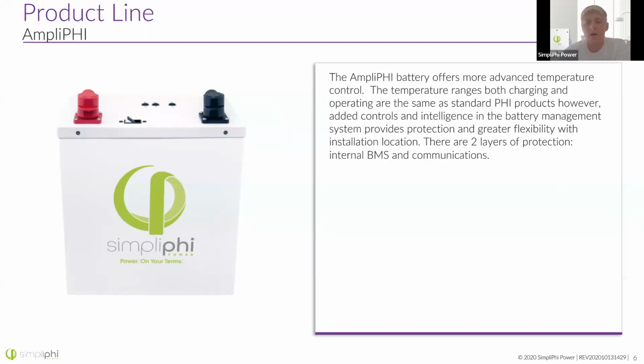The BMS provides two layers of protection. One layer is the actual communications ports on top. The battery will communicate with a compatible inverter charger, and in turn the inverter charger will listen to the battery's commands. So the battery will tell it, hey, I'm getting cold, I'm going to need you to slow down this charge rate, or maybe even shut off charging entirely, depending on temperature.